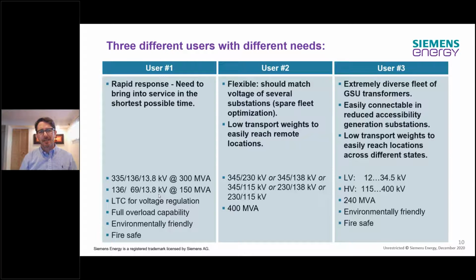He said, ideally I should also be able to operate this unit in another substation with 136 to 69 to 13.8 kilovolts at 150 MVA. He said, I definitely need an on-load tap changer for voltage regulation.